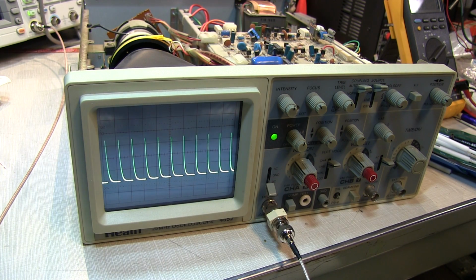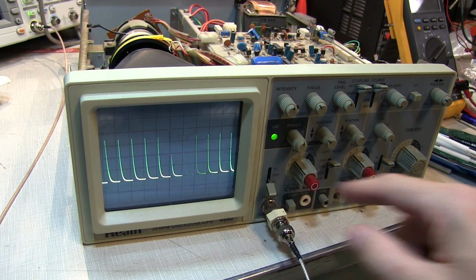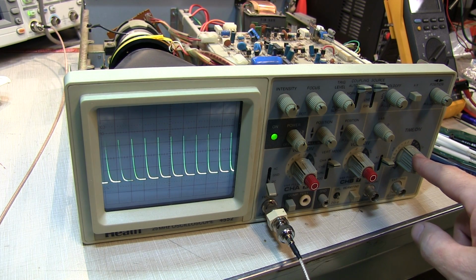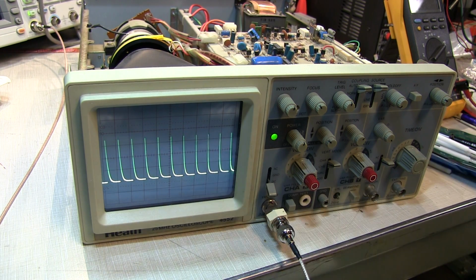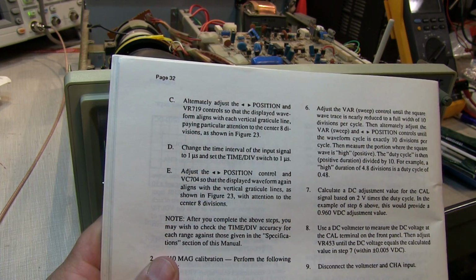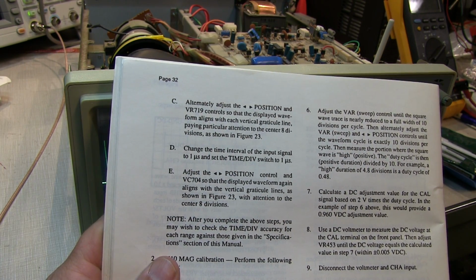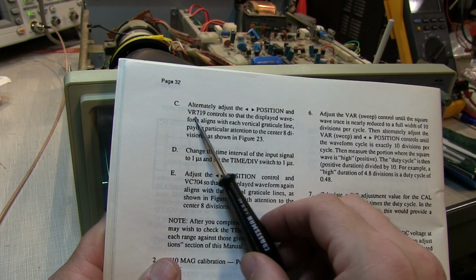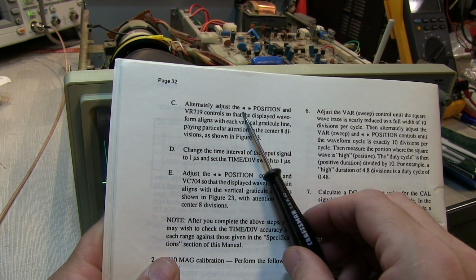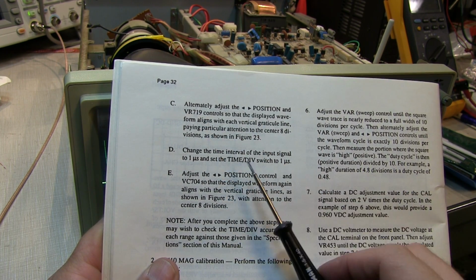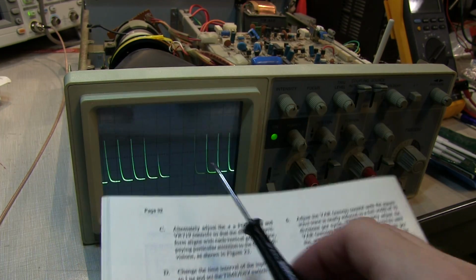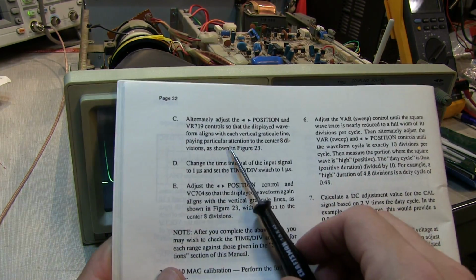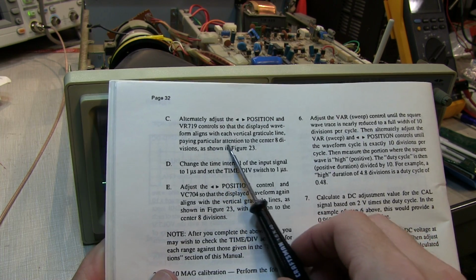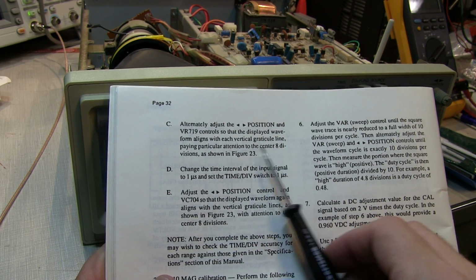Next we apply a time mark signal to the input. Start off with a 1 millisecond period for that time mark signal, and also set the time base to 1 millisecond per division. We can see from the instructions here that what we need to do is adjust the control for this, and also adjust the position back and forth so that we can get all of the pips effectively to line up with the vertical graticule lines. And there's a special note here to pay particular attention just to the center 8 divisions.